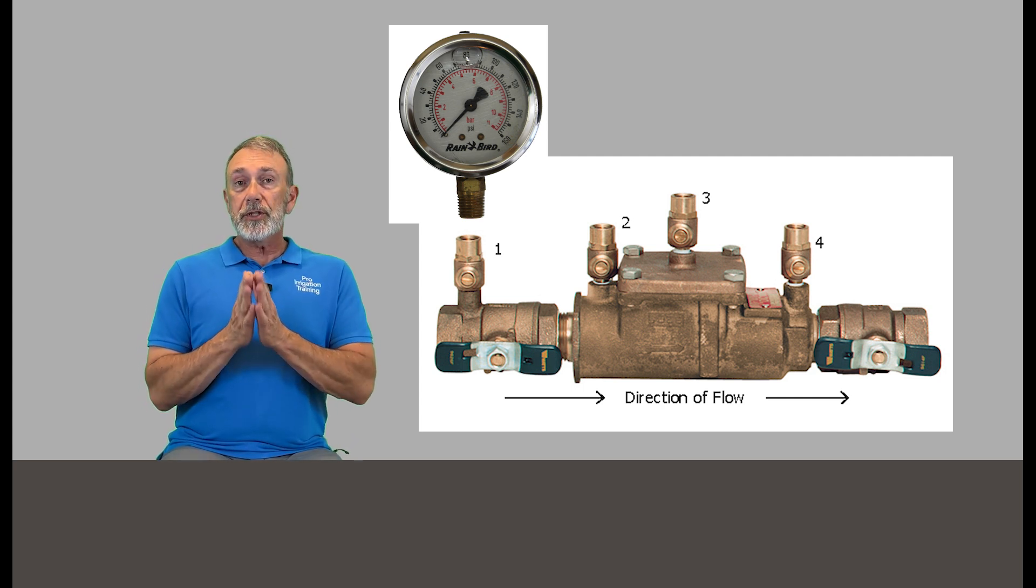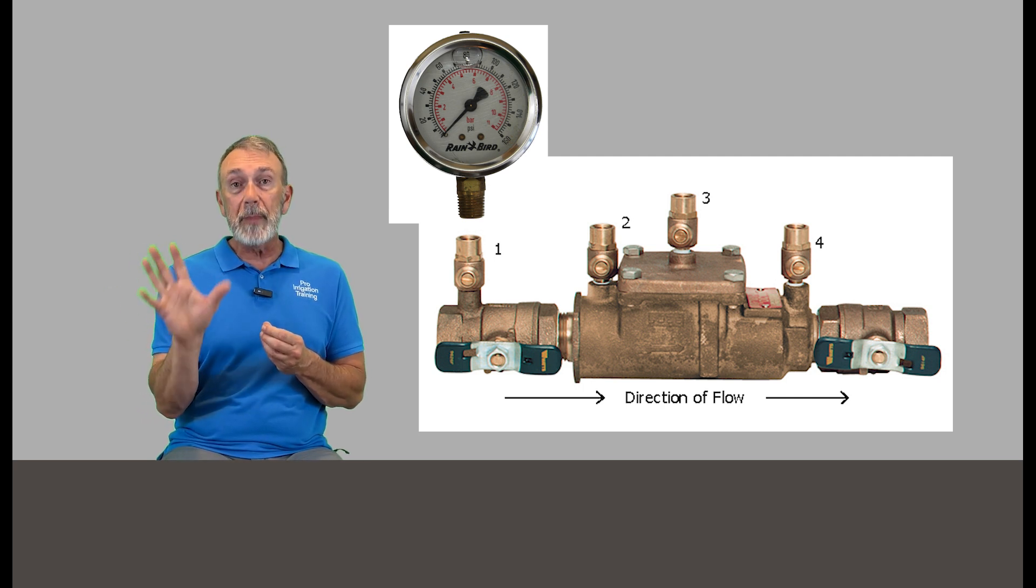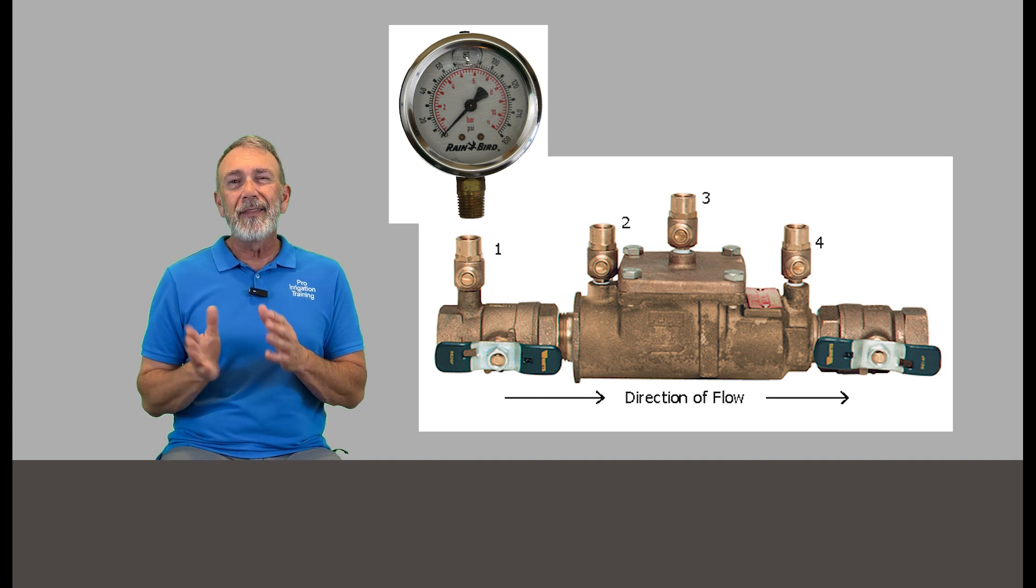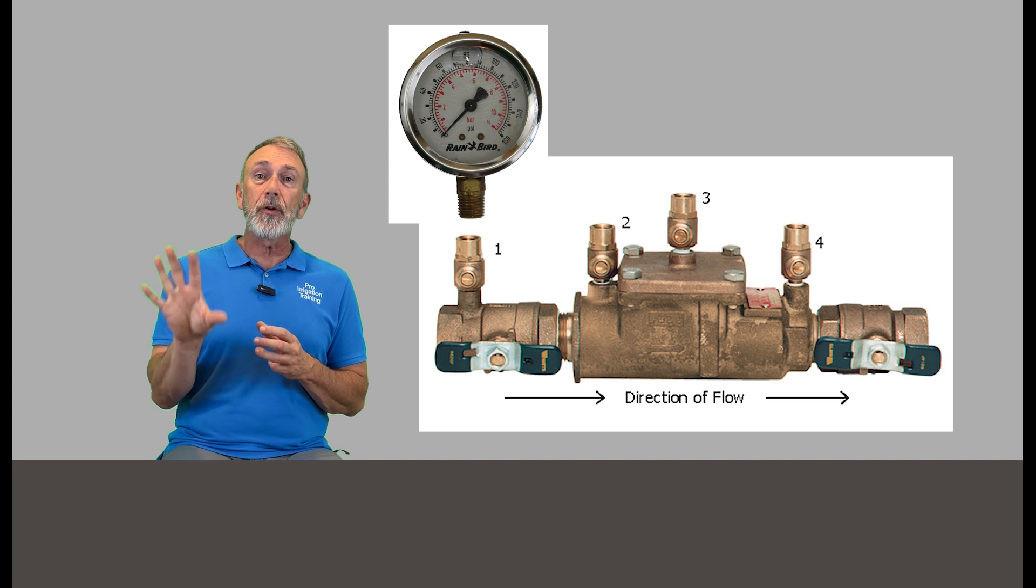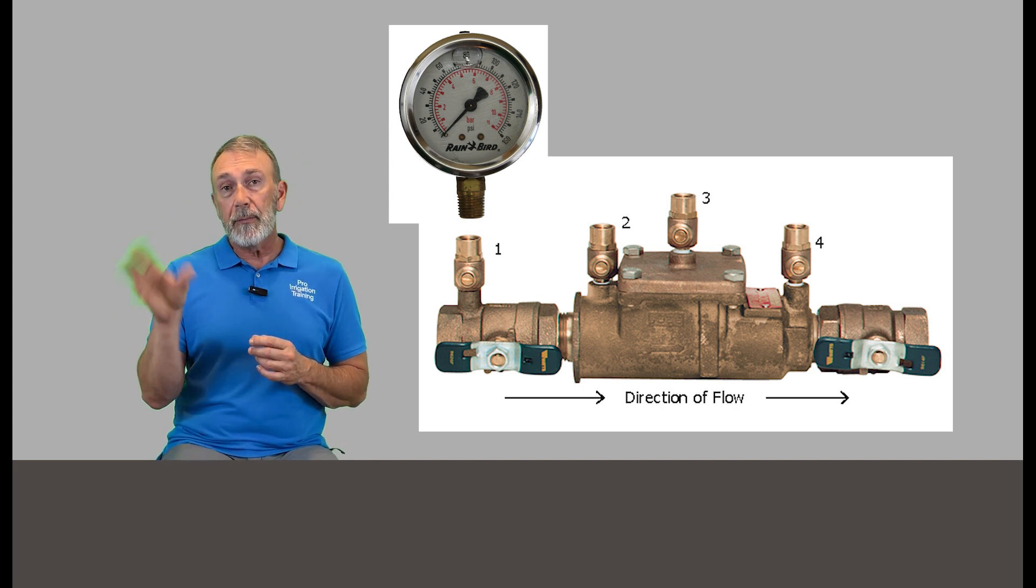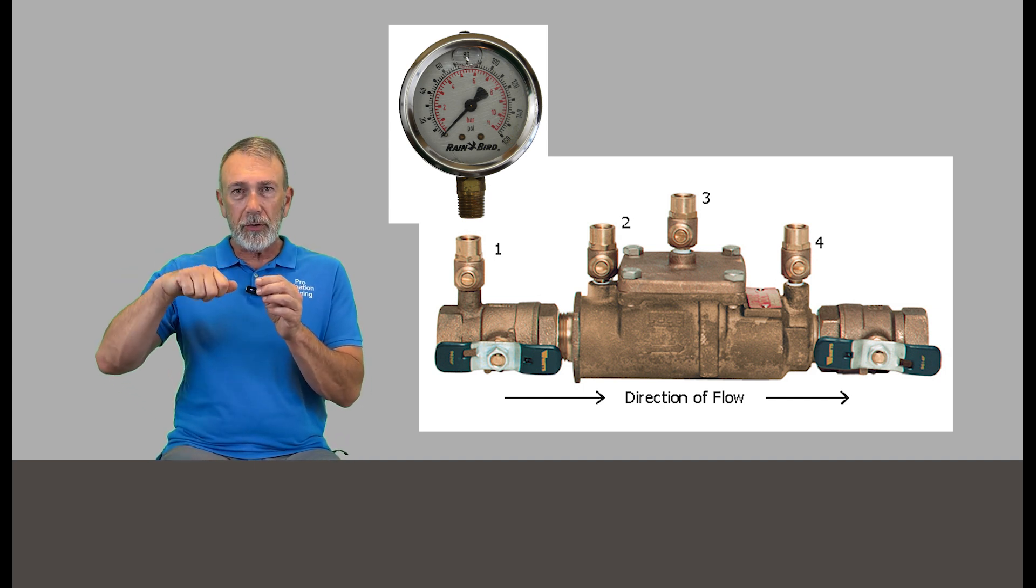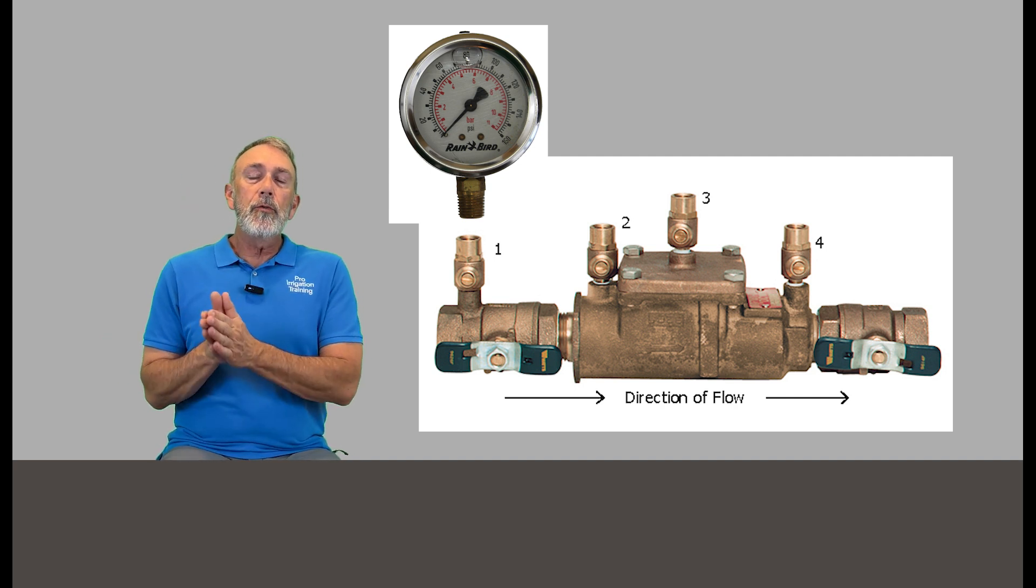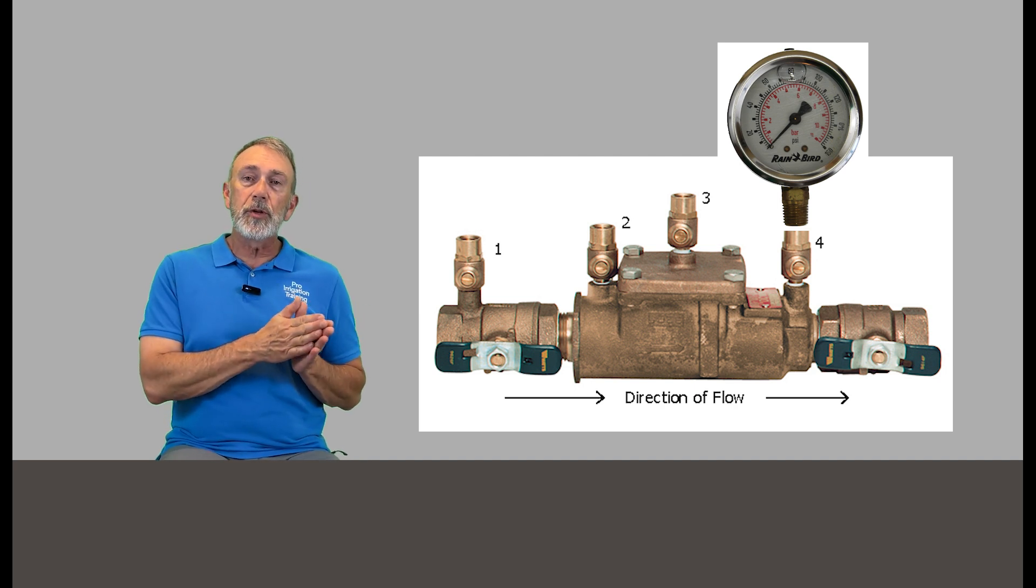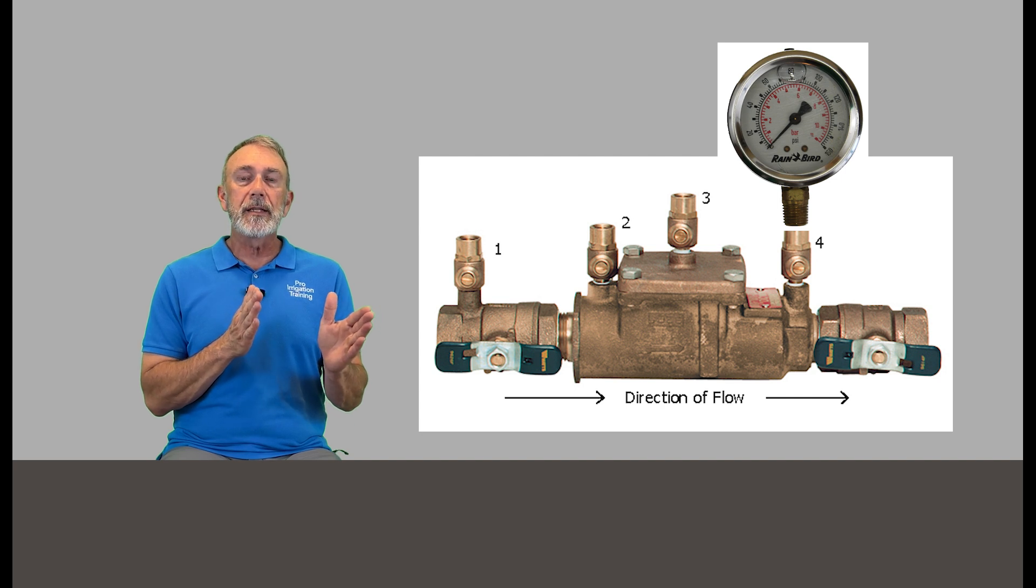We're going to put our gauge on test cock number one. This is the test cock that's closest to the meter. This should give us a good and clean reading of what our input pressure is. And if you put your gauge on there and it reads lower than what you were expecting, then it's a problem with the meter, the water meter or the curb stop or whatever your supply point is. And that's usually not the purview of the technician that belongs to the water system. You're going to have to call your water purveyor and have them come out and address the meter.